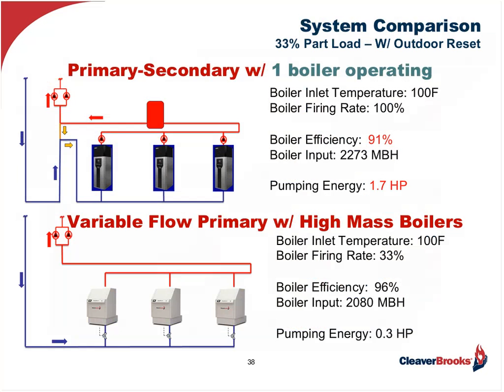Now, just to reverse, so what if we shut one boiler off and match the flow rate? You might think that would save you some energy, and it does, but look at what happens here. You're using less pump horsepower, but you're still not going to be as efficient as the primary flow systems, mainly because now your firing rate has gone up to 100%, and you've lost efficiency there.